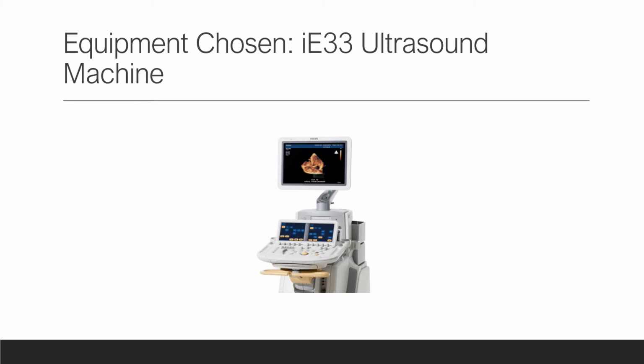A clear distinction of how this machine operates is oscillations release mechanical energy in the form of high-frequency sound waves that are transmitted to the body in pulses. As the sound waves travel through the body, they are reflected, refracted, and transmitted as they interact with the body's internal structures. This is then returned by reflecting the sound waves to the transducer, where it is then converted into a voltage. This voltage is then transmitted to the CPU, where the board filters the signal, resulting in the formation of a digital signal.